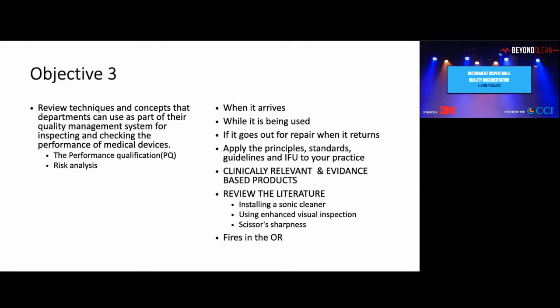The PQ - performance qualification, IQ, OQ, PQ, risk management. You want to do this when it arrives and when it's being used. What if it goes out for repair and gets returned? Apply the principles, the standards, the guidelines, and the IFU to your practice.